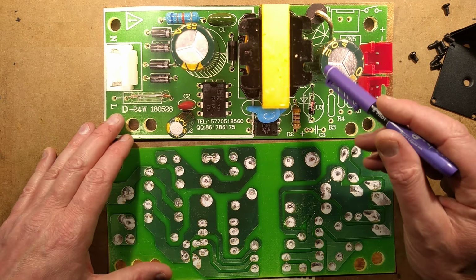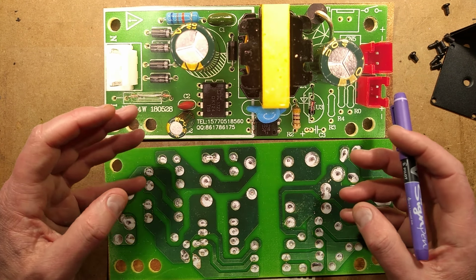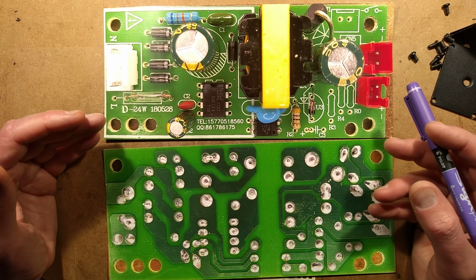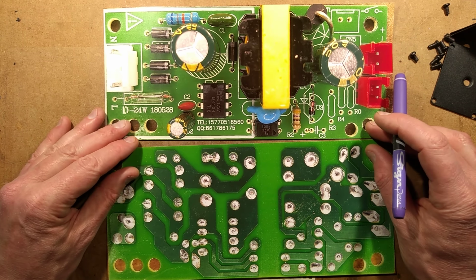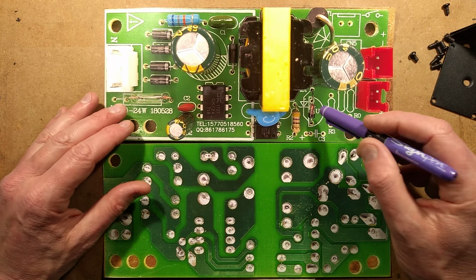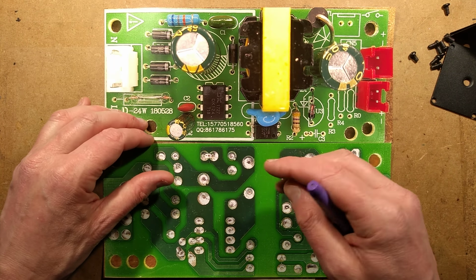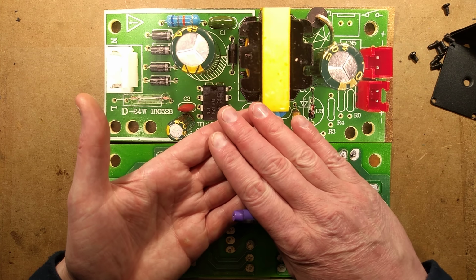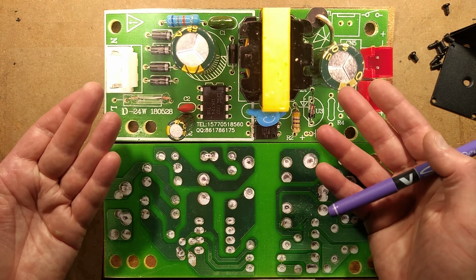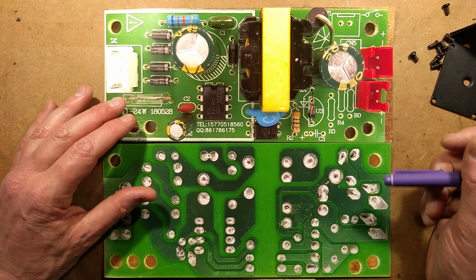Goodness knows how good the transformer is. You'd have to unwind it to see how good it was. You could do a high voltage test, but that only goes so far. As these units age, if there's wires crossing, the high voltage test may be passed, but over time when the insulation breaks down, it may cause a problem.